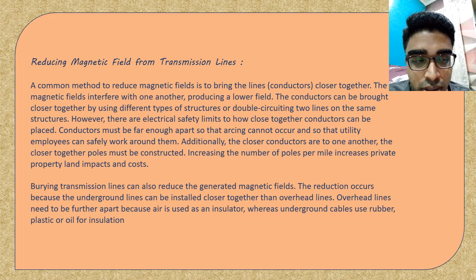Underground transmission lines can also reduce the generated magnetic field. The reduction occurs because underground lines can be installed closer together than overhead lines. Overhead lines need to be further apart because air is used as an insulator, whereas underground cables use rubber, plastic, or oil for insulation.